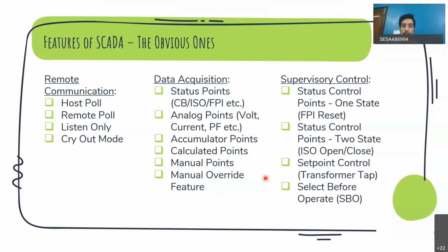Third one is listen only mode. This is generally used when you are upgrading your existing SCADA. You have an existing SCADA application which is running since the past X years, and you want to replace it with a better version. So rather than doing it on one fine day, you'll make both the systems run in parallel so that you gain confidence on the new system. During that time the new system will be running on listen only mode - it's like read only mode. So it is getting data from the field, but it is not doing anything. You can compare both the old and new systems to see if there is any difference.